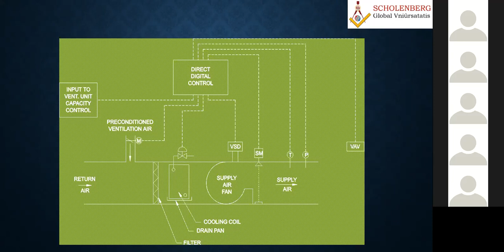So this is all the VAV system control. Just for comparison purposes, consider a single duct multiple zone with VAV and a single duct constant volume multiple zone, just to see the difference. What are the facilities here? If you have a VAV single duct multiple zone, you have various zones, and the VAV system has advantages. At the terminal, you can have more control. Depending upon the load, the terminal will control the flow of air and the temperature. Whereas we have limitations on the other, when the load is fixed, so here we use this type of constant volume system with multiple zones also.